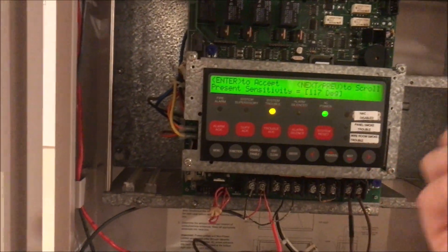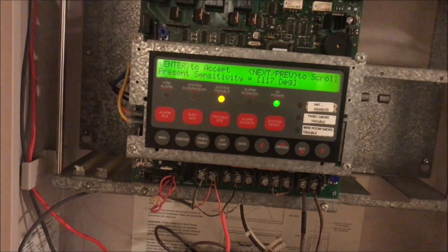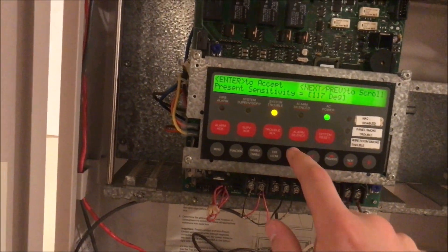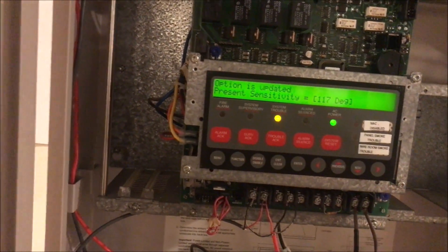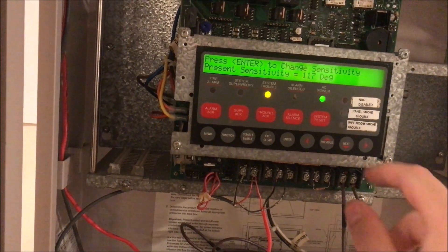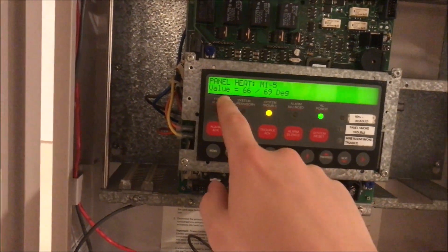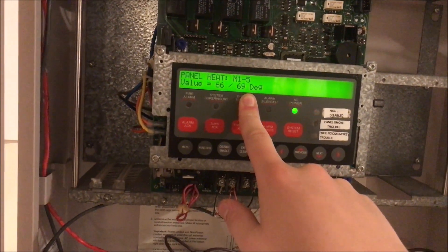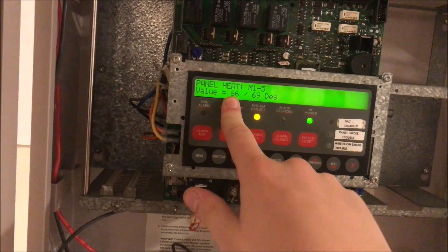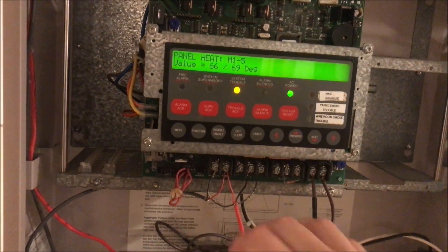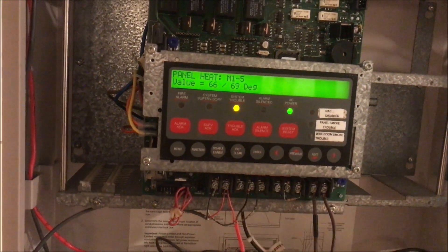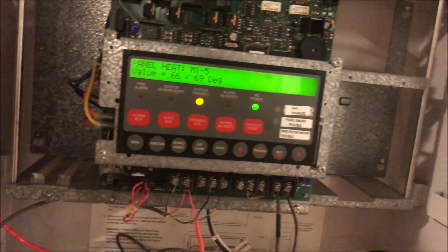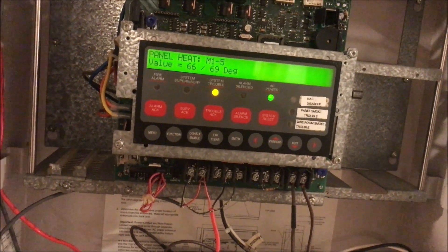For the sake of the video, I'm leaving it at 117 because that's a lower activation temperature, so it's just easier to work with. You can also go in and see what it is currently sitting at. The way that this is read is rate of rise over fixed temperature. We're only going to be looking at the fixed temperature part of this for the sake of this video because, frankly, it's easier to interpret and more relevant.